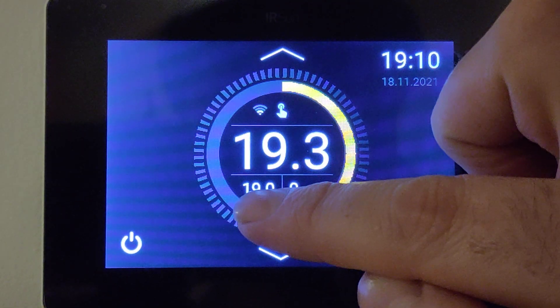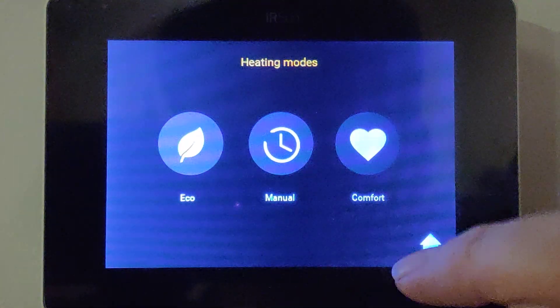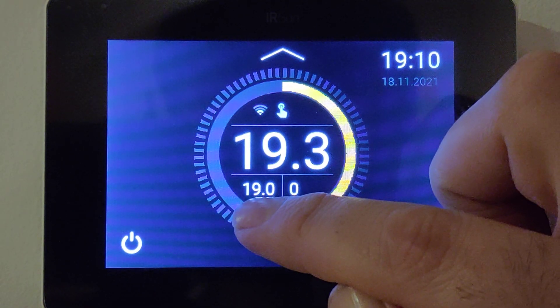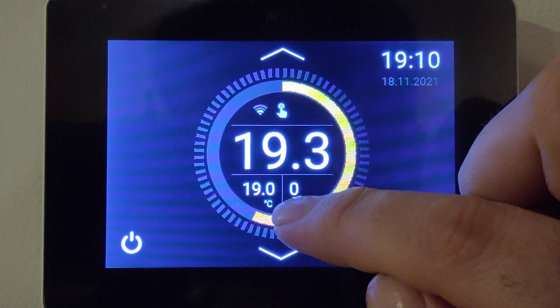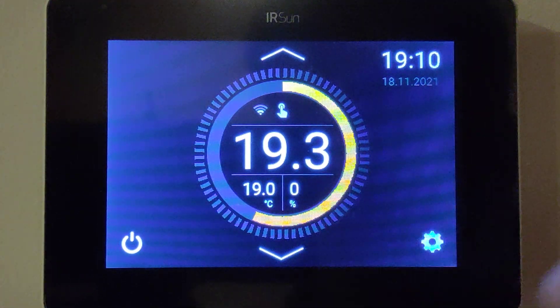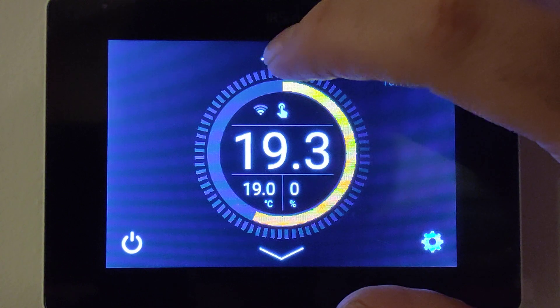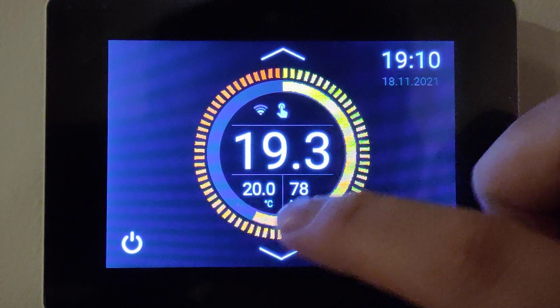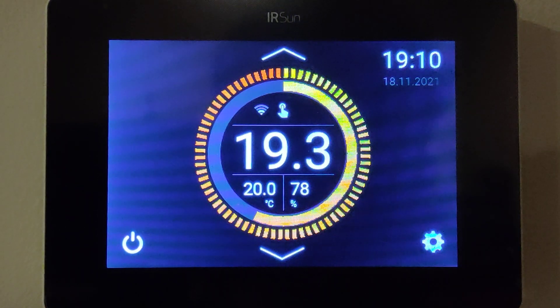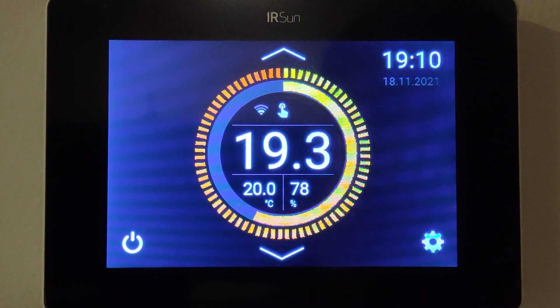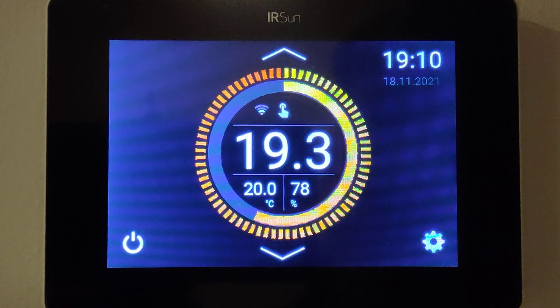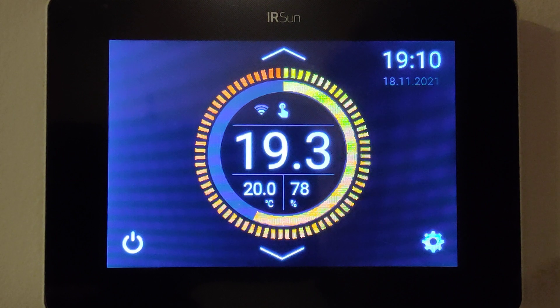Then we hit the back button and the home button. This is the set temperature, which is 19 degrees, and this is the percentage of output of the heater. So if I want to achieve 20 degrees in the room, it's now using 78% of the total wattage of the heater to bring the temperature from 19.3 up to 20 degrees.